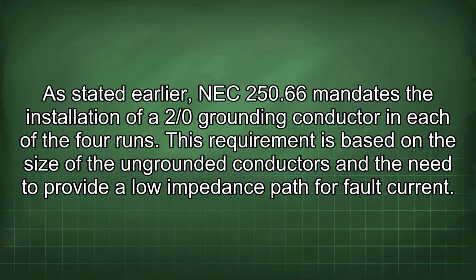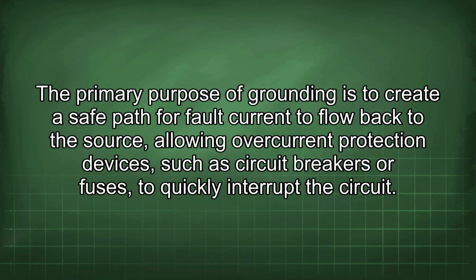This requirement is based on the size of the ungrounded conductors and the need to provide a low impedance path for fault current. The primary purpose of grounding is to create a safe path for fault current to flow back to the source, allowing overcurrent protection devices, such as circuit breakers or fuses, to quickly interrupt the circuit.